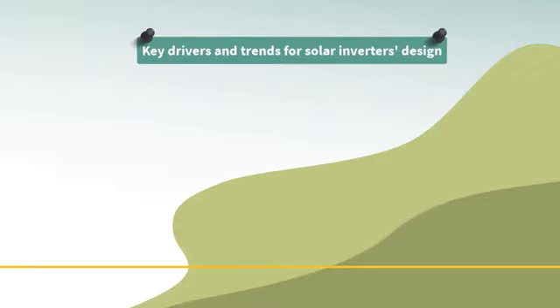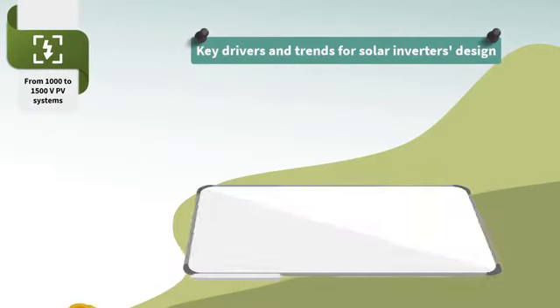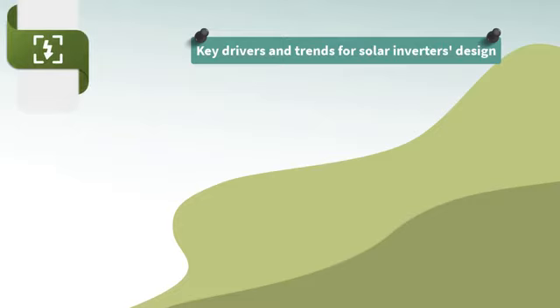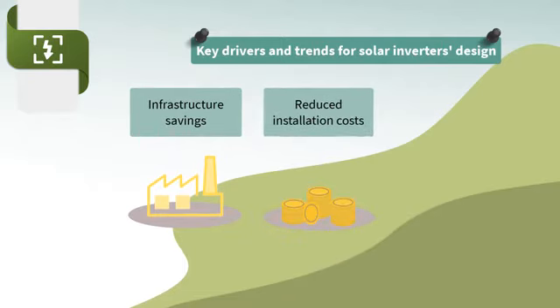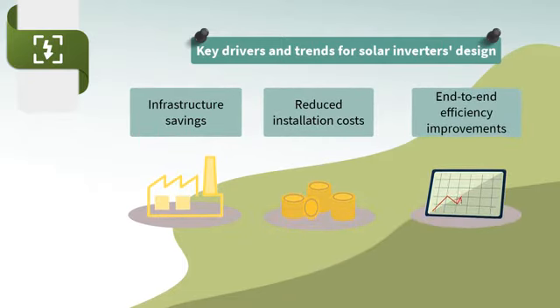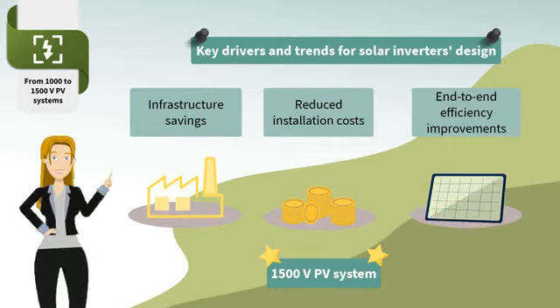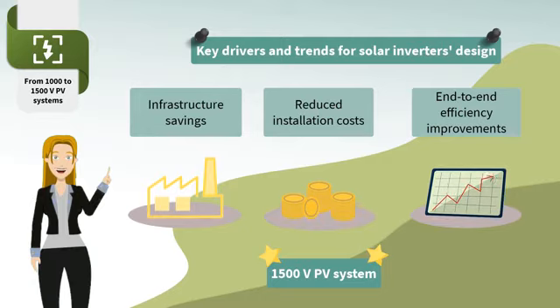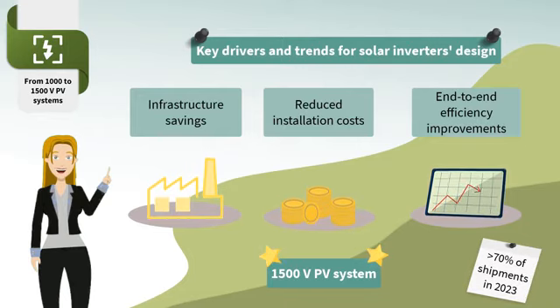The key drivers for the solar inverter's design are system costs and end-to-end efficiency optimization. One of the major trends in utility-scale PV solar projects is the change from 1000 to 1500 volt systems. Basically, the value of increased system voltages translates into infrastructure savings, reduced installation costs, and end-to-end efficiency improvements. As time goes by, it is expected that the 1500 volt PV voltage will be the mainstream for utility-scale installations. In fact, 1500 volt PV inverters are expected to account for more than 70% of the three-phase PV inverter shipments in 2023.